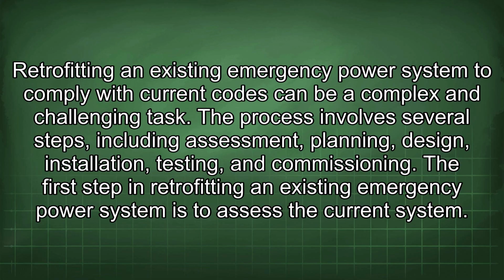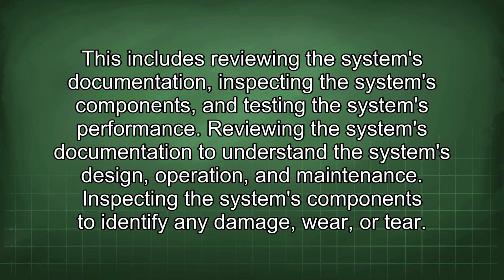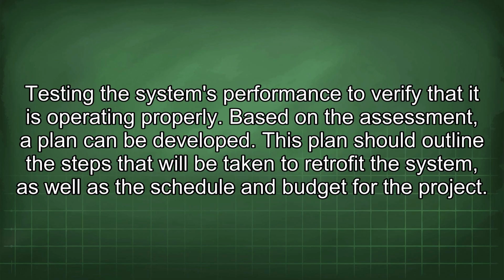The process involves several steps, including assessment, planning, design, installation, testing, and commissioning. The first step in retrofitting an existing emergency power system is to assess the current system. This includes reviewing the system's documentation, inspecting the system's components, and testing the system's performance. Reviewing the system's documentation helps to understand the system's design, operation, and maintenance. Inspecting the system's components identifies any damage, wear, or tear. Testing the system's performance verifies that it is operating properly.